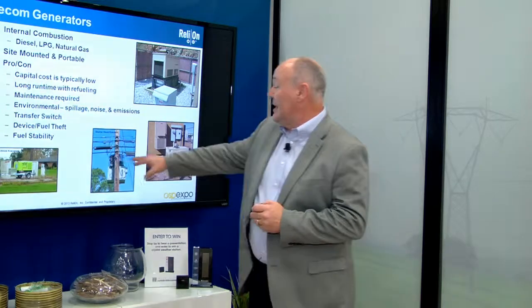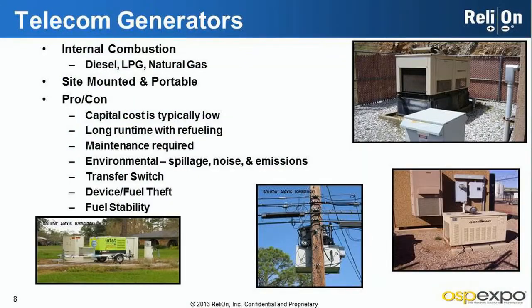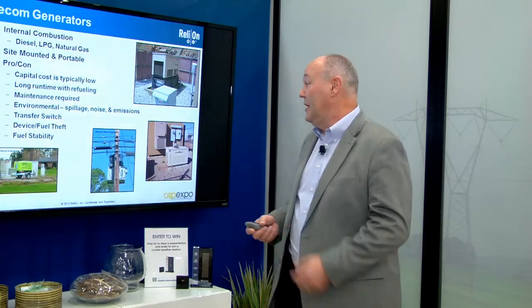Most of these gensets are AC devices. This one being an exception, this is a DC generator here. But if it's an AC genset, it needs to have a transfer switch so you don't back power the grid, causing a safety hazard to someone else at the grid site.